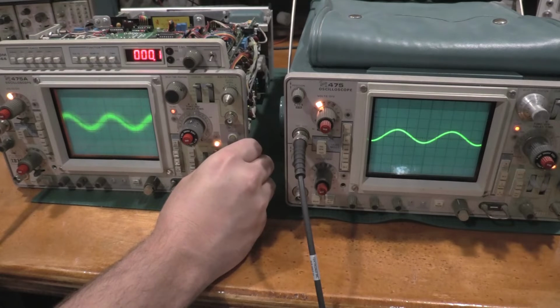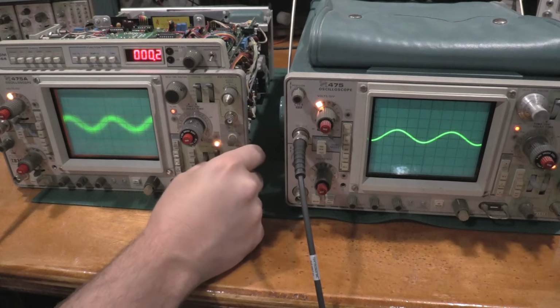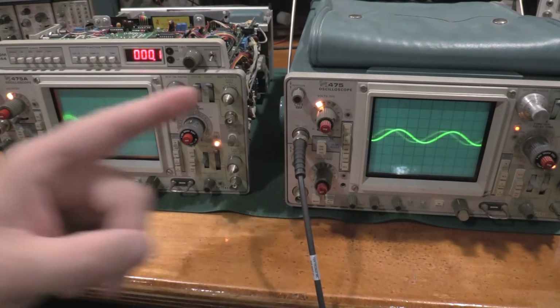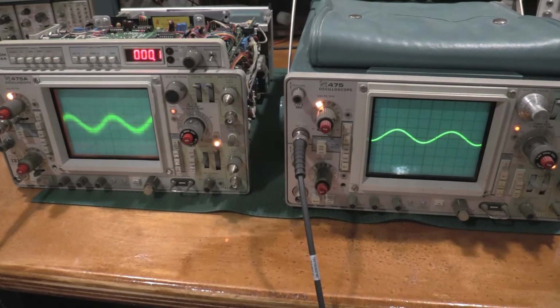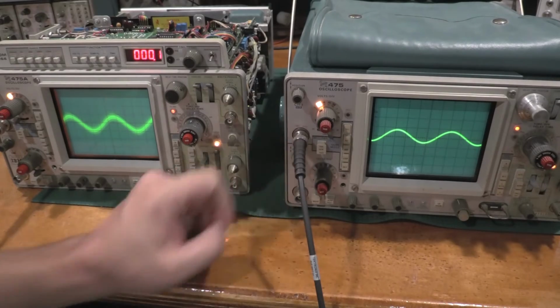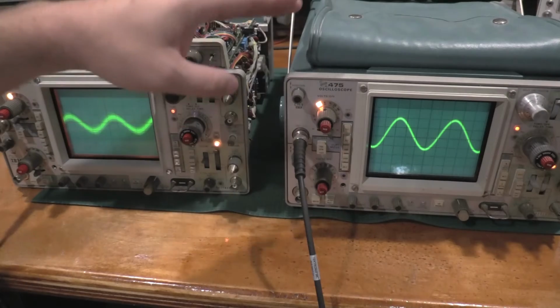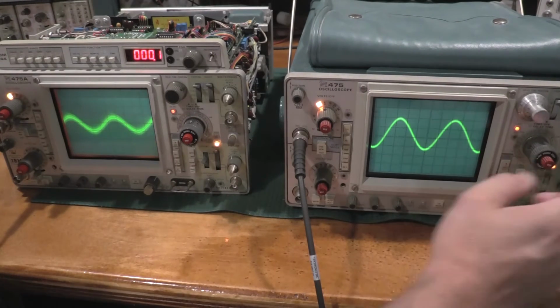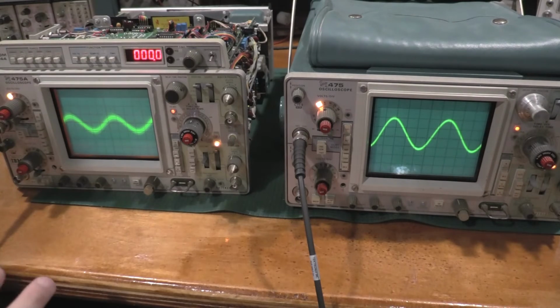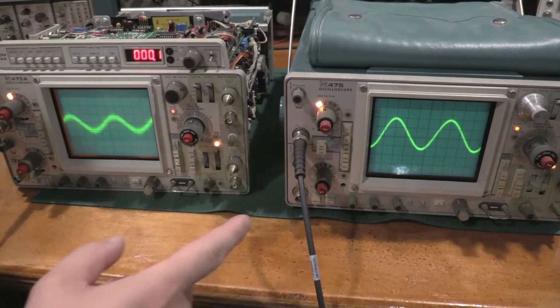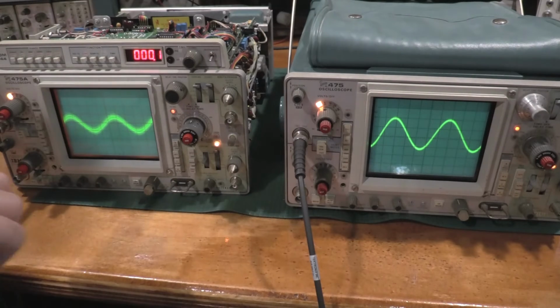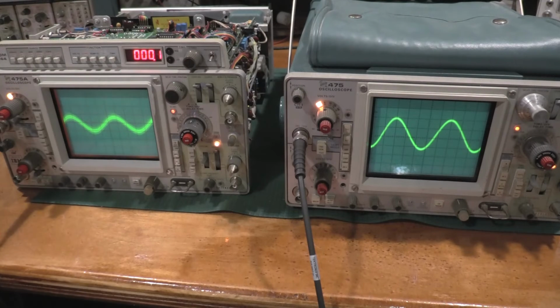Okay, let's see if we can answer, does the scope suffer performance degradation? Keeping in mind that I have not serviced this unit yet at all. I have serviced this unit, and it's good to go. This one's been finished. Now, one thing I did notice is on the 475A, we go down to 5 millivolts per division. On the 475, we actually have a 2 millivolts per division range, so I can go down one more. So I also have more spaces on the time base on the 475 as well. Funny thing is, these are spec'd differently. So the 475 is a 200 megahertz scope, where the 475A is a 250 megahertz scope. So a little bit of weirdness there.